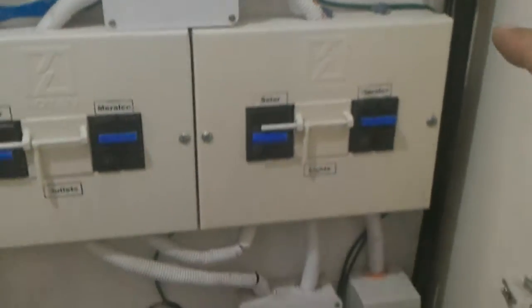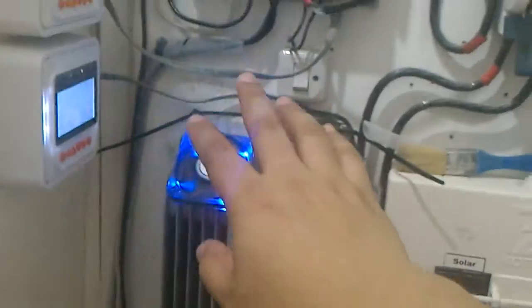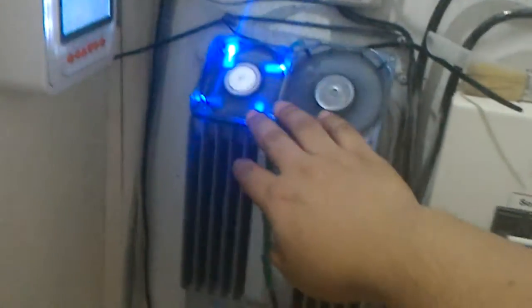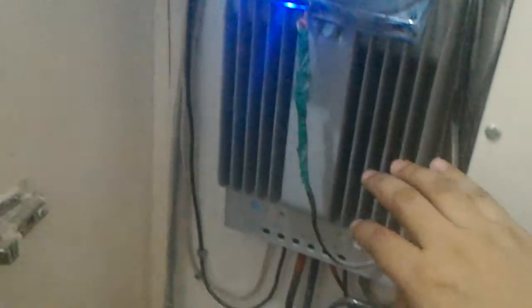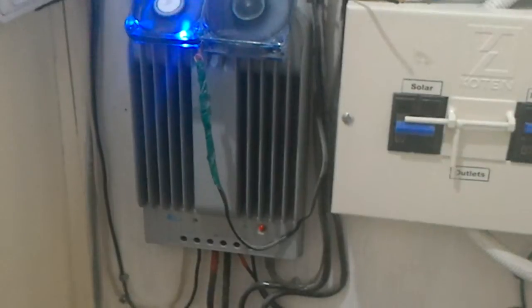This solar charge controller acts as a low voltage disconnect so I can control the depth of discharge of the battery and not over-discharge it. It's currently set at 12 volts or 30% depth of discharge. I installed fans to keep it cool.